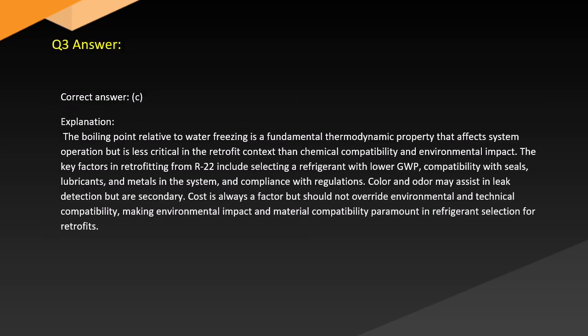Answer. Correct answer, C. Explanation. The boiling point relative to water freezing is a fundamental thermodynamic property that affects system operation but is less critical in the retrofit context than chemical compatibility and environmental impact. The key factors in retrofitting from R22 include selecting a refrigerant with low GWP, compatibility with seals, lubricants, and metals in the system, and compliance with regulations. Color and odor may assist in leak detection but are secondary. Cost is always a factor but should not override environmental and technical compatibility, making environmental impact and material compatibility paramount in refrigerant selection for retrofits.